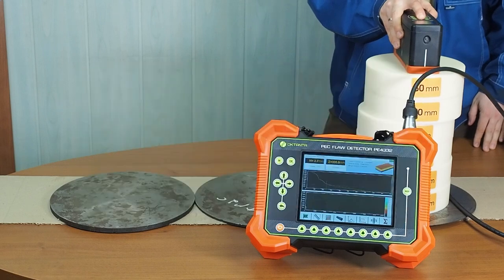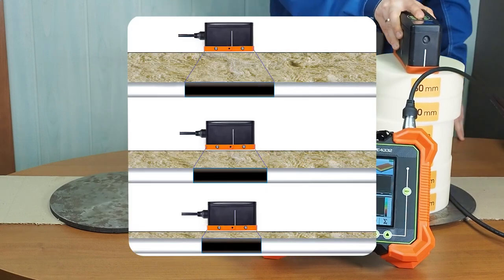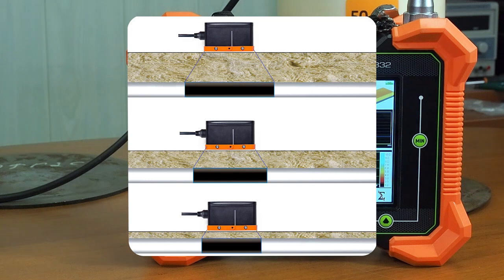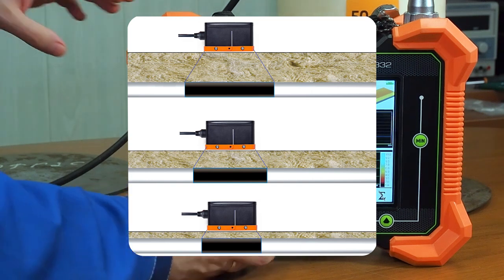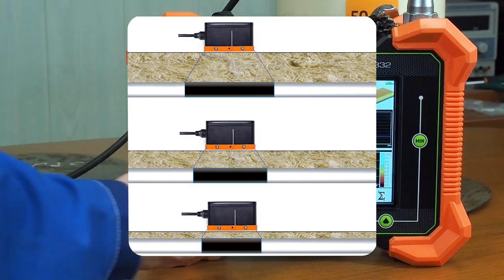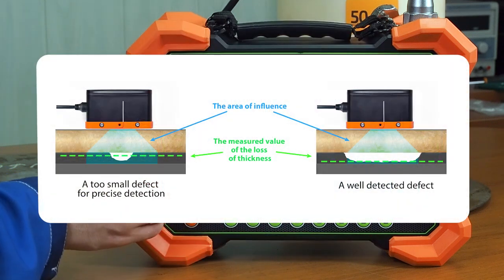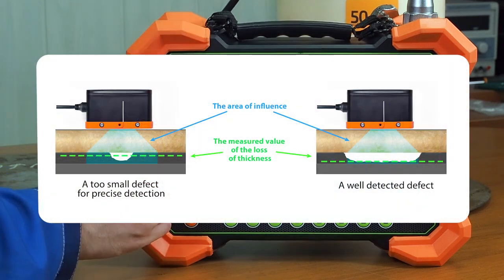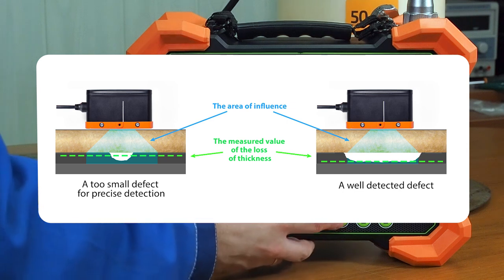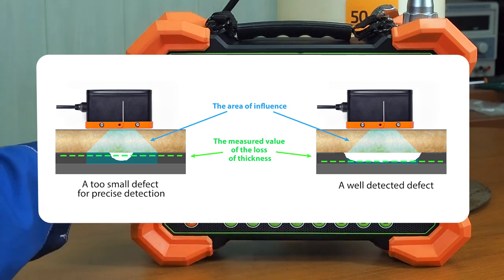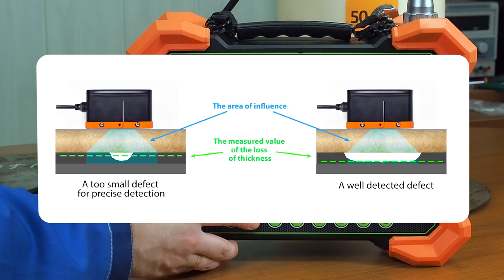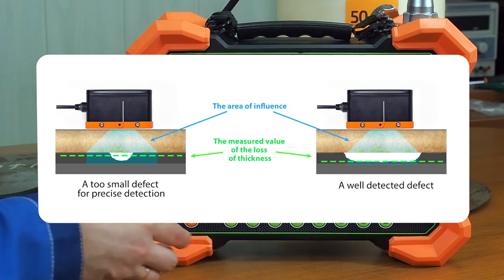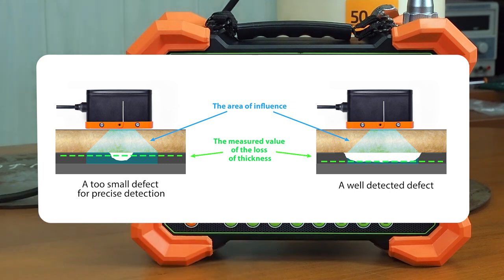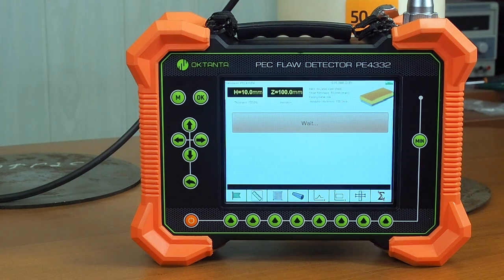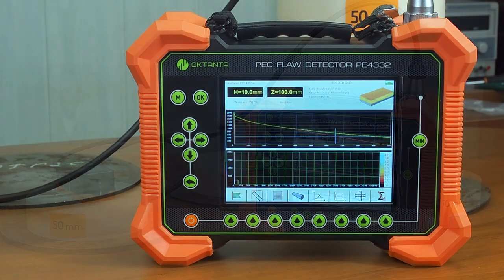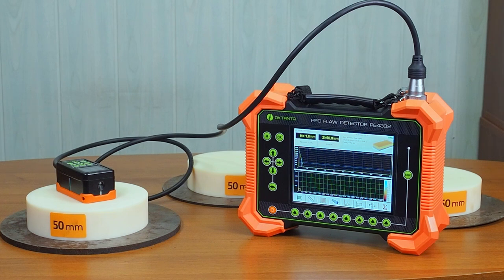the demagnetization rate. The sensor has a working aperture comparable to the size of the sensor itself. About 90% of this area provides a response signal to the receiver of the device transducer. Due to this measurement method, we won't be able, on the one hand, to see small cracks and defects that are significantly smaller than the sensor surface. But on the other hand, the device perfectly measures large areas of corrosion through the insulation and casing. Let's skip directly to the measurements, starting with a small sensor and a small insulation thickness of 50 mm.